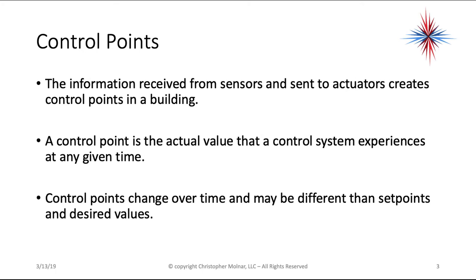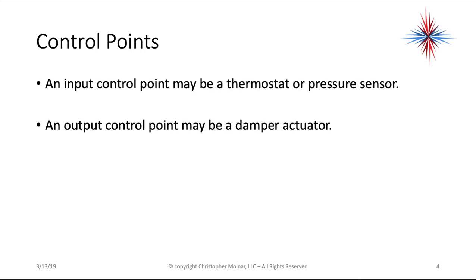Control points are information received from sensors and sent to actuators, creating control points in the building. A control point is the actual value that a control system experiences at any given time. Control points can change over time and may be different than set points and desired values. An input control point is a thermostat or a pressure sensor, collecting information and sending it to a controller. An output control point may be a damper actuator, a valve, or perhaps a fan control.